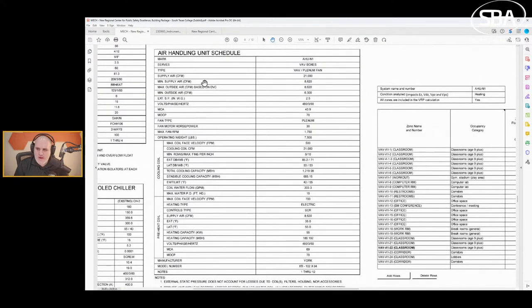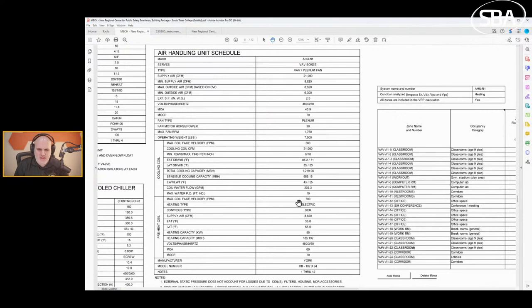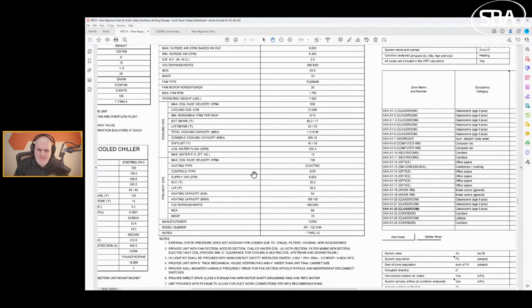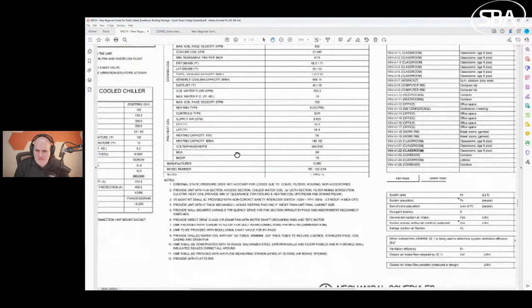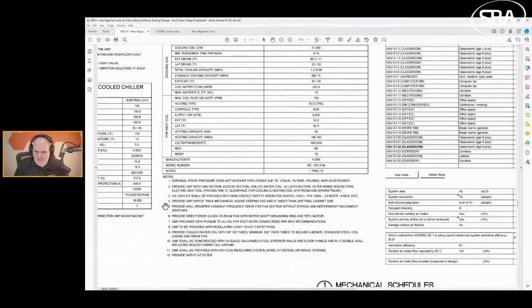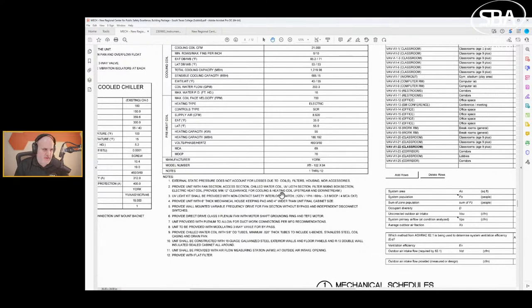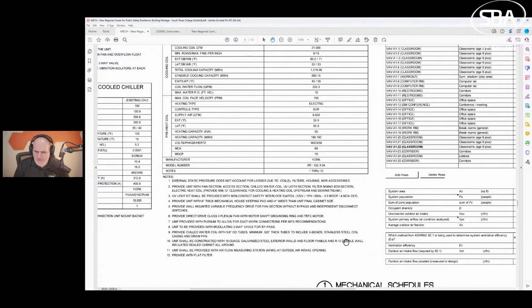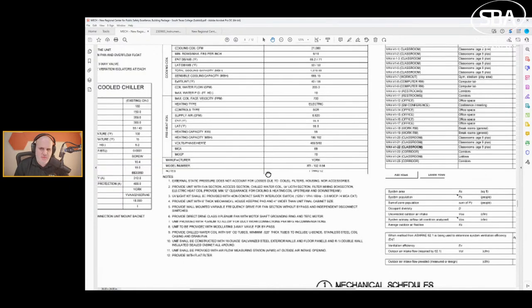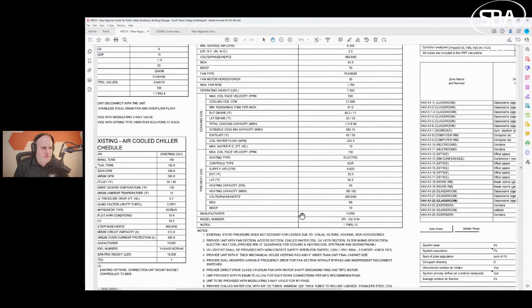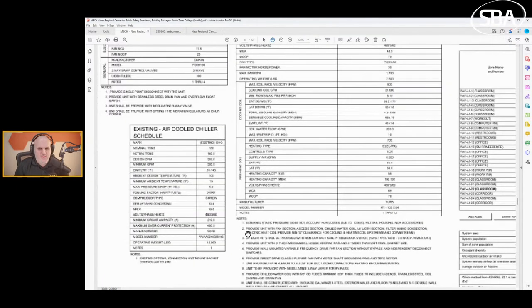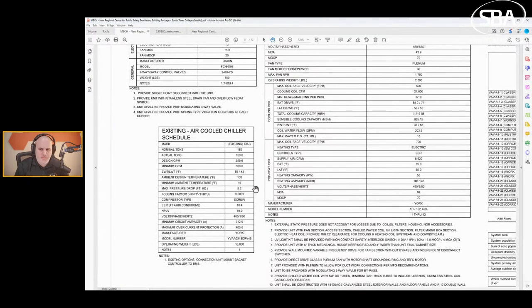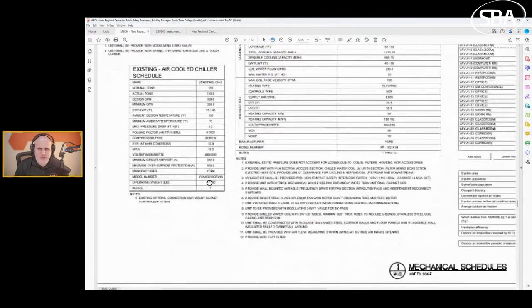We should have some exhaust fans in here. These all look like constant volume exhaust fans. They should be provided with motor switch, flexible duct, damper. We don't know who provides that. Interlocked with the associating air handler unit serving the same zone. Watch notes carefully because sometimes all the notes will not be applicable to all the items.